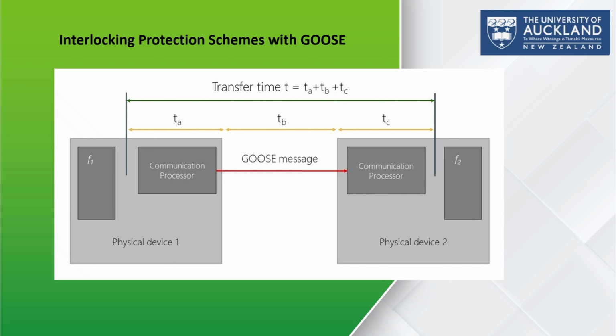So the performance class is the highest performance class, I mean the P2 and P3 of the IEC 61850 standard, demanding a total transmission time below the order of a quarter of a cycle. Therefore, the limit is set to 3 milliseconds. The following image demonstrates how the transmission time is defined in IEC 61850 chapter 5. The trip is the most important fast message in a substation network, and for this reason, the speed performance requirements are particularly high. However, such speed can also be necessary for other operations, including interlocking, intertrip, and logical discrimination between protection functions, right?